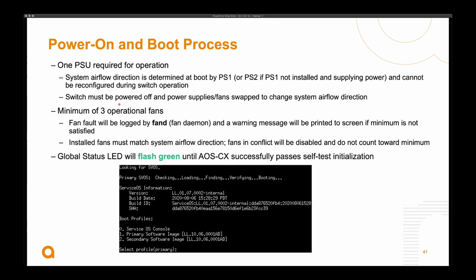To change the airflow direction, you have to actually power the switch off, remove all power supplies and fans, and exchange them for power supplies and fans for the airflow direction you desire. So if you want to switch from a back to front to a front to back power supply, you have to actually physically power the switch off and exchange all of the power supplies and fans so that they all match your desired airflow direction.